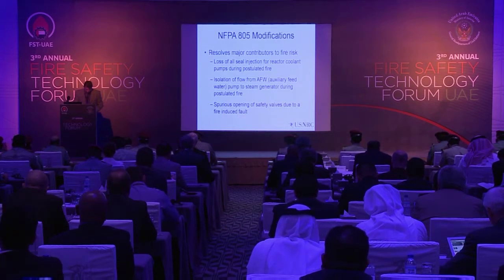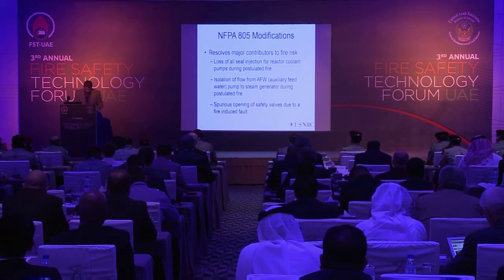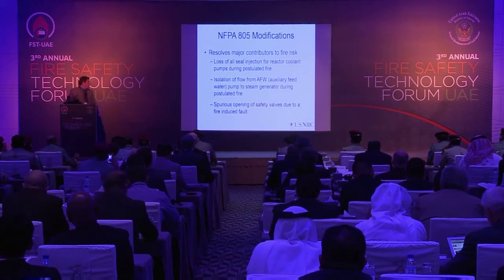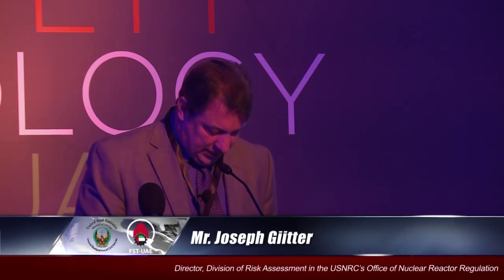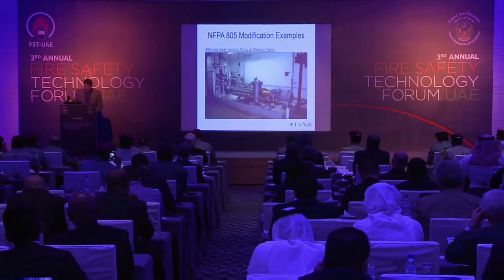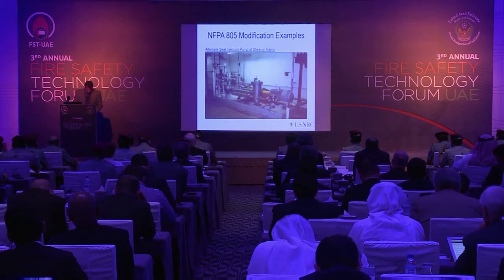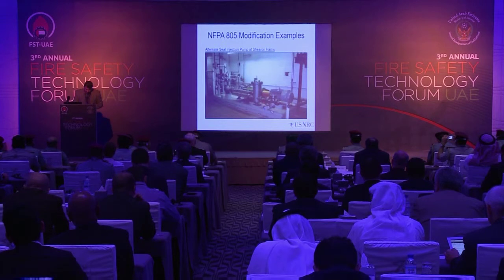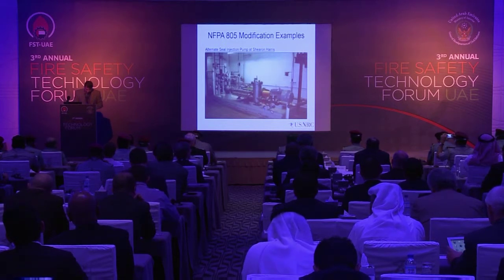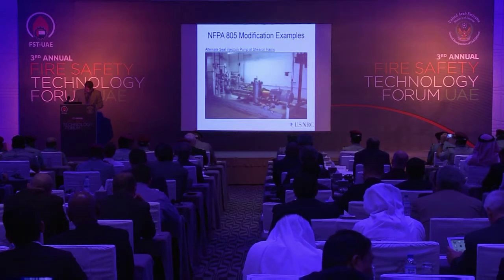To address the loss of seal cooling for reactor coolant pumps, Shearon Harris installed a new alternate seal injection system. Here's a photograph of the alternate seal injection pump. It includes a dedicated diesel generator and a dedicated charging pump to supply coolant to the reactor coolant pump seal. And it also has additional ability to power battery chargers. The alternate seal injection pump was installed to address fire risk issues as part of the NFPA 805 transition and to improve accident mitigation for internal and external events. So when they did their probabilistic safety assessment, this was a major contributor for fire risk, but it was also a major contributor in other areas as well.